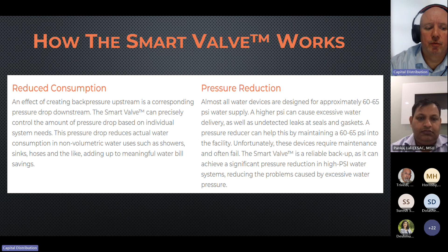Here's some of the internals on the smart valve, and on the larger sizes, what you have is a two-stage valve, meaning that the setting determines how much of a pressure differential it takes for the first stage to open. So the amount of demand and the pressure drop downstream will trigger that, so you can achieve the balance you need. If this were to be set at 100, which I'm going to go back to the wrong slide. As you see here on the left side, there's an actual dial on the 3-inch and above sizes. If you were to set that to 100, you would see almost a complete shutoff. And if you're setting it at 0, you should see no change.